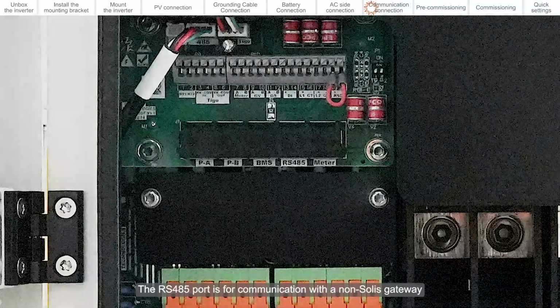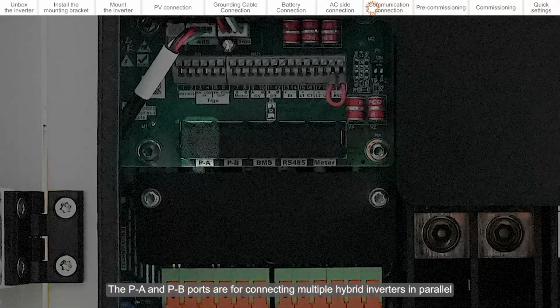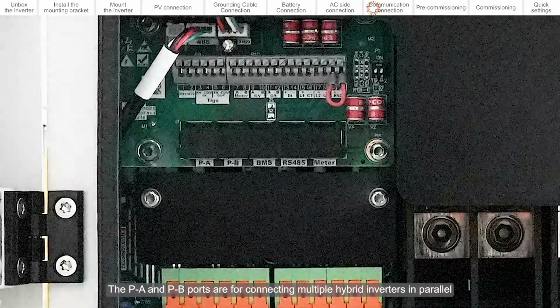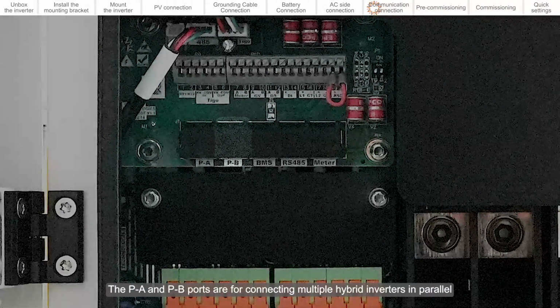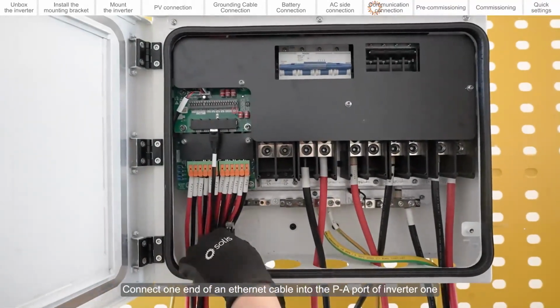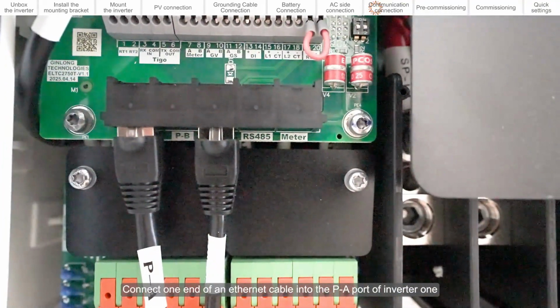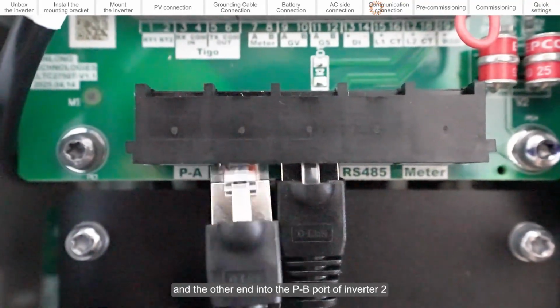The RS485 port is for communication with a non-Solis gateway. The PA and PB ports are for connecting multiple hybrid inverters in parallel. Connect one end of an Ethernet cable into the PA port of inverter 1 and the other end into the PB port of inverter 2.